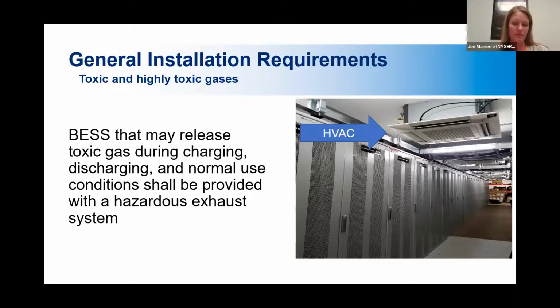But that doesn't mean that a lithium ion energy storage system wouldn't have some type of exhaust, because they might have it installed anyway as a form of explosion control, like we were talking about before. If gases start to build up to a certain amount, there needs to be some sort of explosion control in place. So it could be an exhaust system or that deflagration venting that I was talking about before, which is basically panels that open when they're triggered by too much pressure in the space.